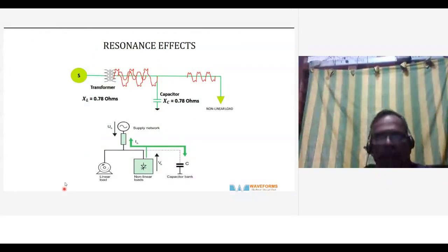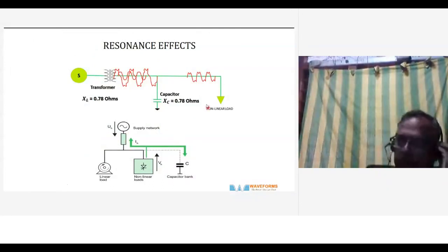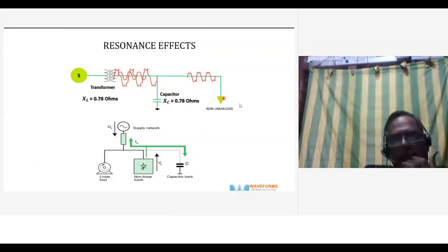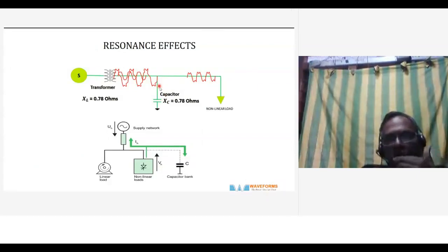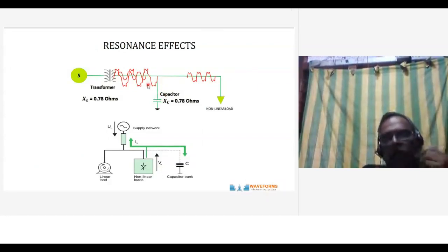See, when you have a transformer with its inductance and a capacitor, and XL is equal to XC, so XL is 0.78 ohms and XC is 0.78 ohms. At a particular frequency, when it interacts with the harmonics, you can see this non-linear load introduces harmonics. These harmonics tend to flow to the capacitor. When they flow to the capacitor, they interact with it, generate new frequencies, and then amplify that particular harmonic signal. You can see the amplification of harmonics at this stage.